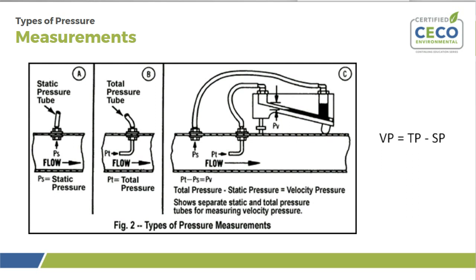Figure B illustrates total pressure. Here, the pressure tube extends into the duct and the tube is oriented so air flows into the tube. And finally, figure C shows the manometer that is used to measure velocity pressure. Normally, we measure only static pressure and velocity pressure and not total pressure. Velocity pressure equals the total pressure minus the static pressure.